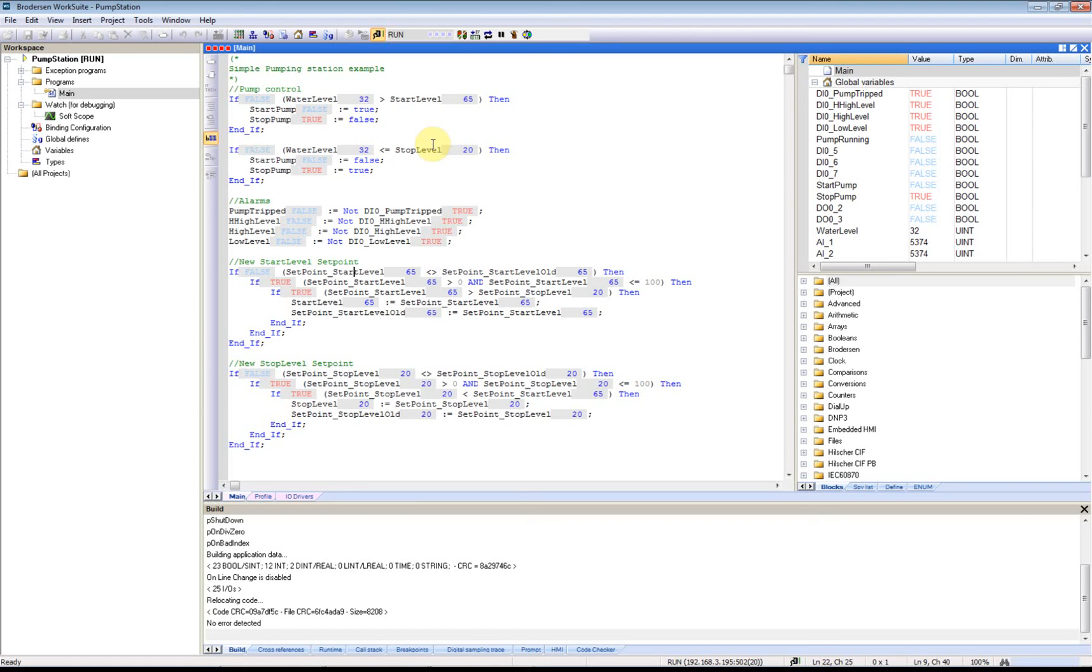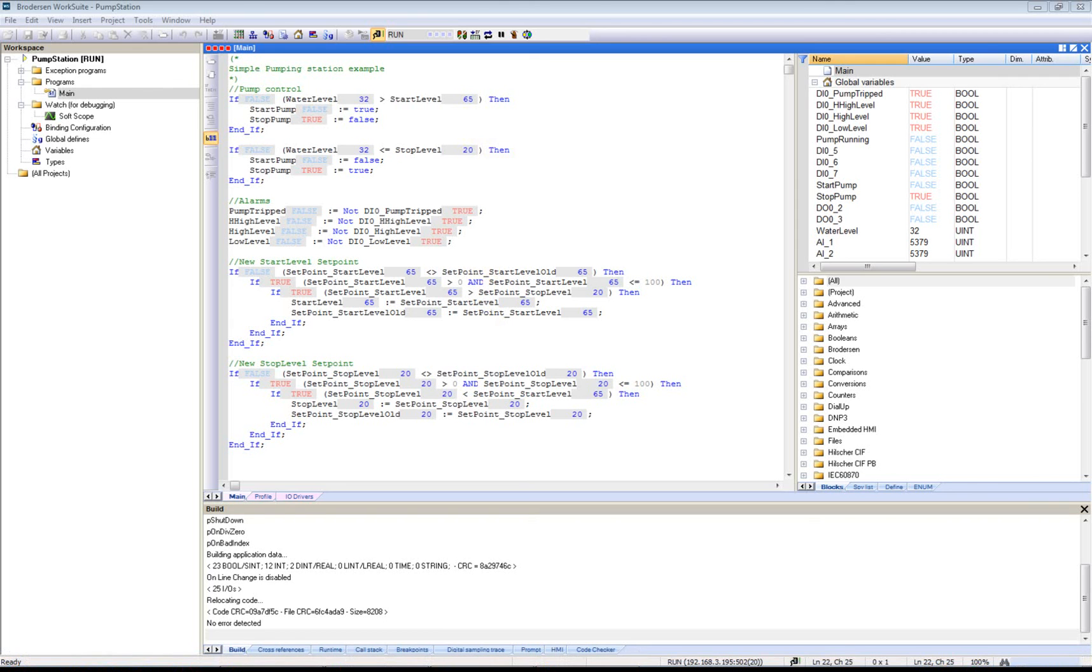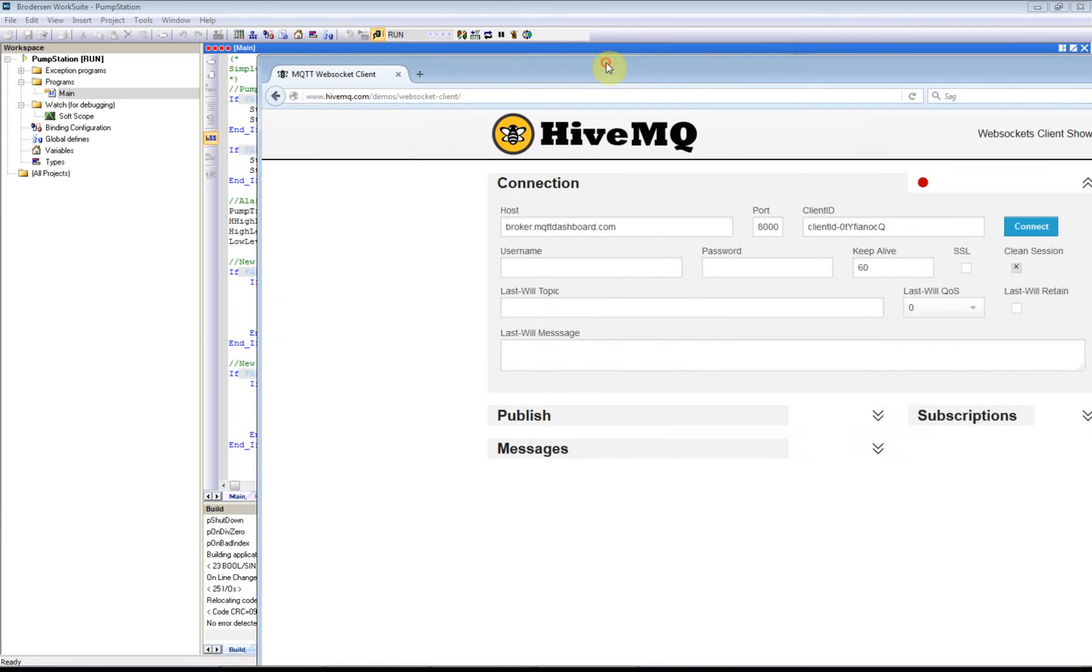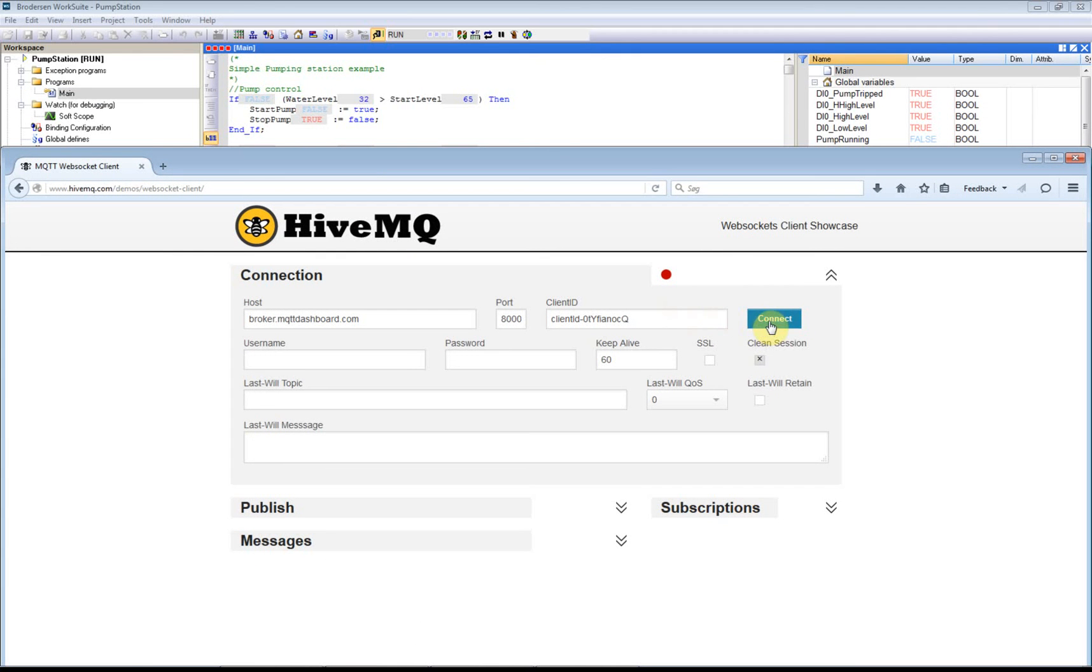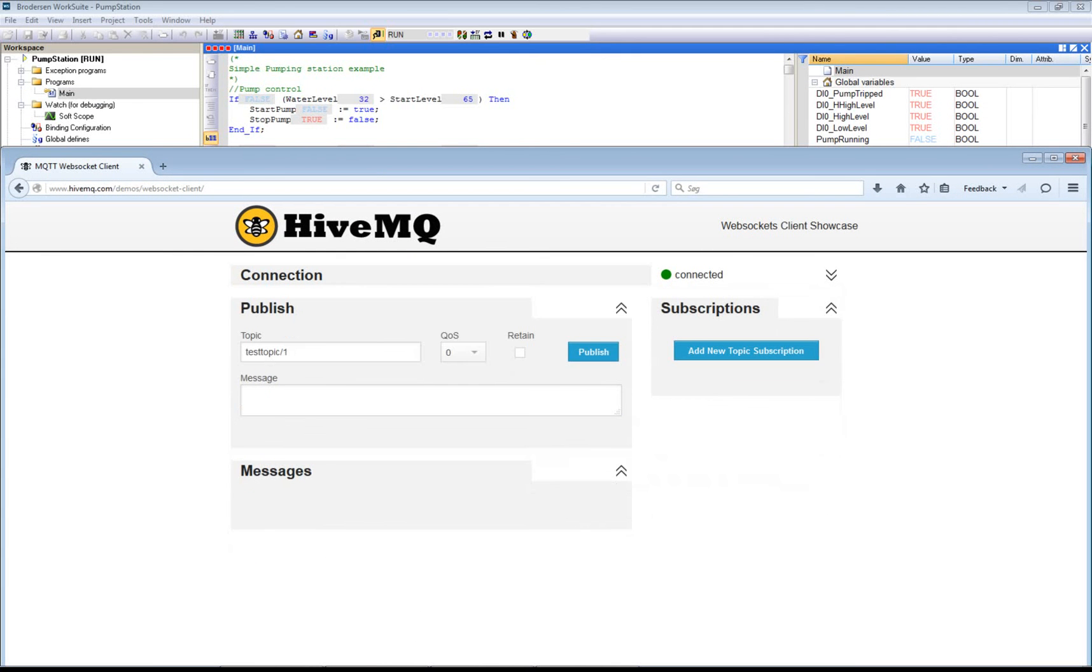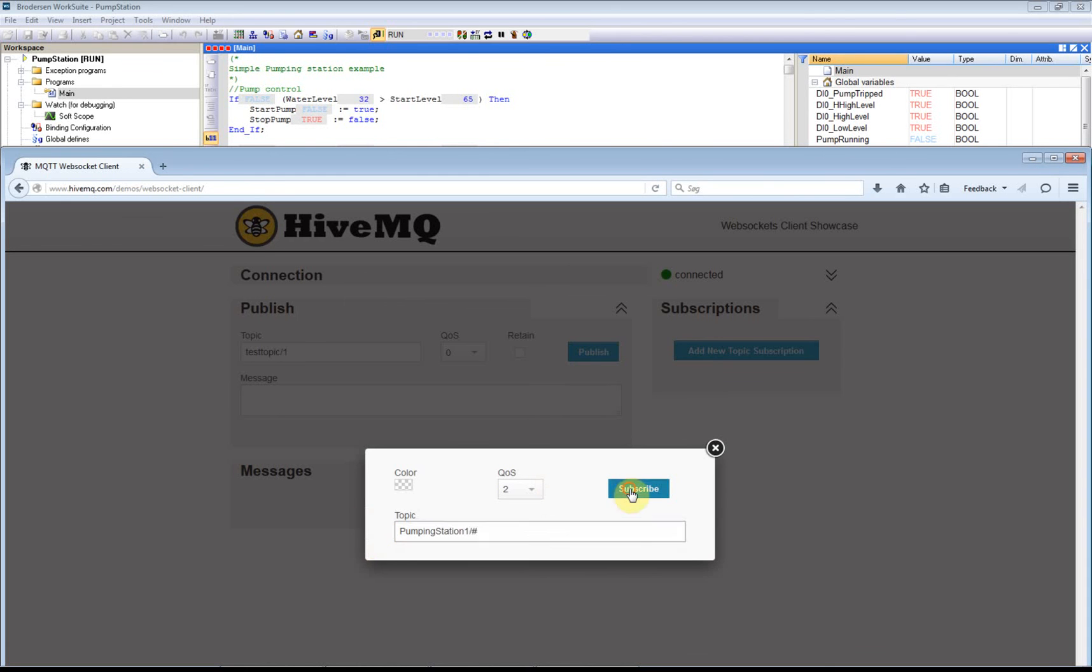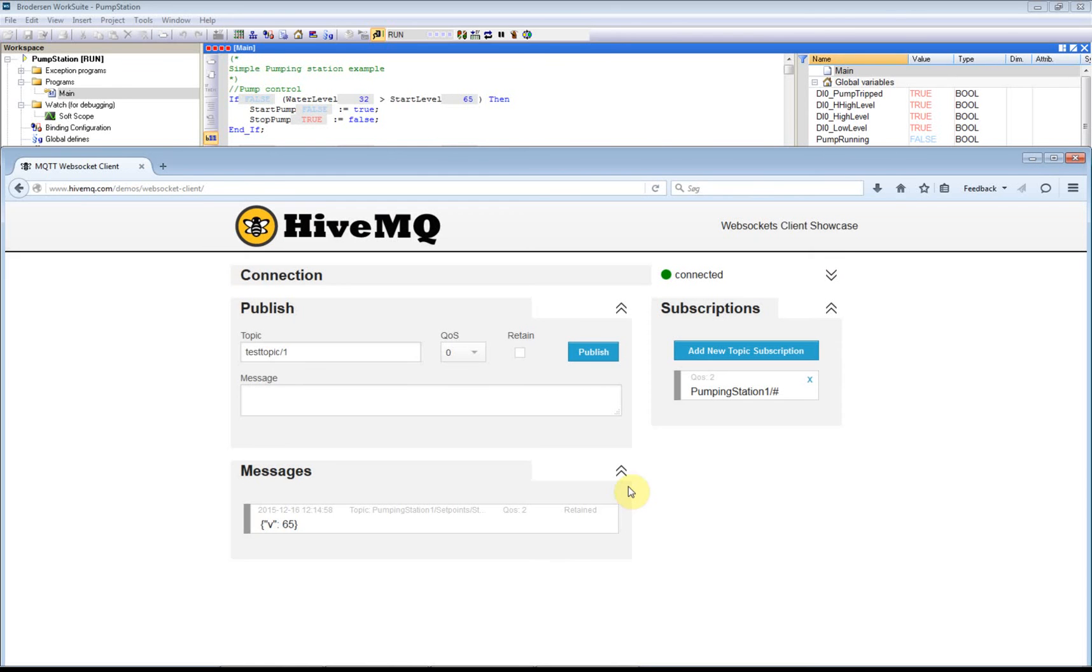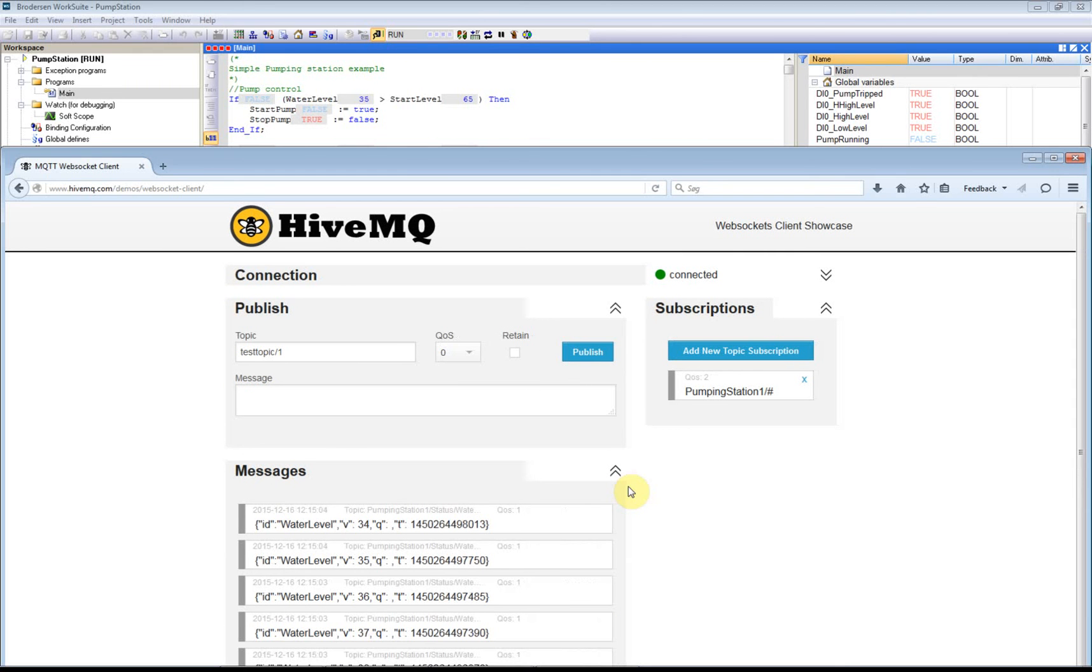Now I will verify that the RTU is actually publishing messages to the broker. I'll start the online broker, which is the one that we connected to. I'll now connect here and subscribe to all events coming from Pumping Station 1. Subscribe. You can actually see now, change the water level, we get the messages.